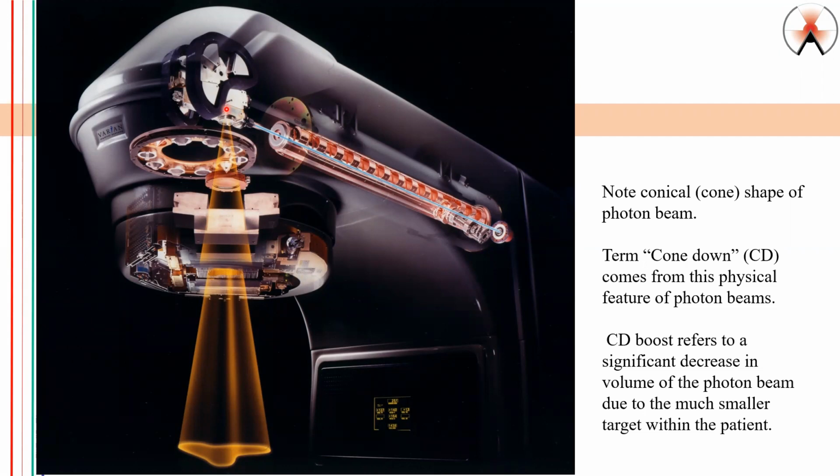And in that violent collision, we convert the electron stream into photons. Inside the collimator is what we call the primary collimators, and these are static. We cannot control them. This limits the opening of the collimator to 40 by 40 centimeters. These are the secondary collimators that we can control with our software, and this is what shapes the beam as it is aimed at the patient.